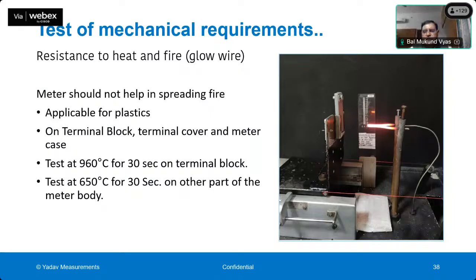Another very important test for the meter is resistance to heat and fire. As I was explaining, if the meter is made of plastic, then this test is applicable. There are two different types of plastic which can be used in the meter. One is for its terminal block where the wires are connected, because those are the areas where the heating can be more. Another plastic which can be used is for the terminal cover or for the meter body. So two different temperatures are specified. One is for the terminal block where wires are connected. Because of load, there can be more heat.